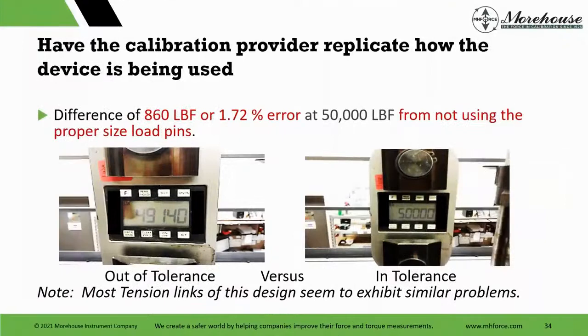Other things, we talk about these. Have the calibration provider replicate how the device is being used. Here's with force, very common error, right? It's pin size. So one pin engages properly, 50 millimeter. One pin is smaller. What happens? Well, when I engage a larger area, I get more strain on the device, and hence I get more output. So here's a situation where manufacturer says 0.1% is the specification here, and all we did was switch pins, one 50 millimeter, about 1.97 inches, and the other pin about 1.75 inches. All we did was switch them.